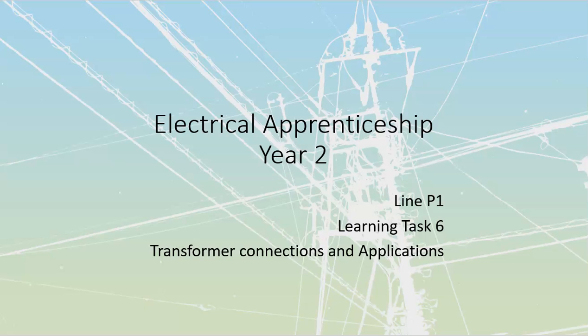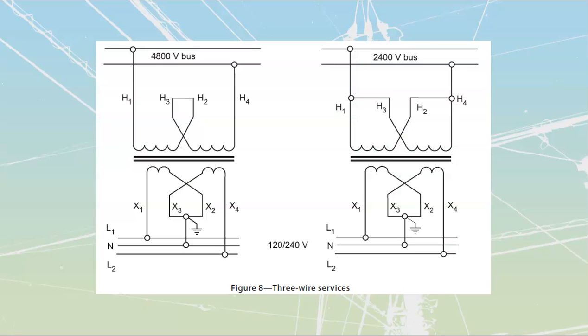All right, line P1, we're taking a look at learning task 6b. We quit after the first section there, it was about 40 minutes already, so we're moving on to the next section. We're jumping ahead to three-wire services because it's an important enough concept that we want to dedicate some time to it. This is a really common transformer layout that we'll see, where we supply our standard single-phase service, a 120/240 volt system. In this case we're using that same 100 kVA, 2400/4800 to 120/240 transformer, and hooking it up to create this three-wire service.